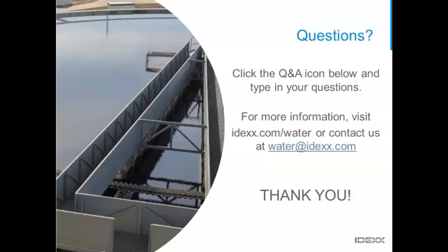All right, thank you. Sean, we talked about a comparator for Colilert. There are two comparative questions for you, sorry. Is there a separate comparator for fecal coliform interpretation? Nope, there is just the one comparator, and that comparator is for both Colilert and Colilert-18. It provides the yellow and fluorescence, and then if you're doing fecal coliform testing, then you just use the yellow.